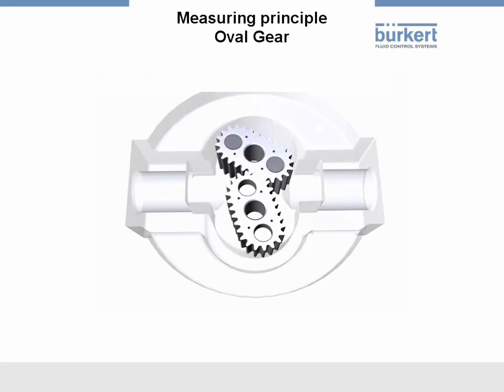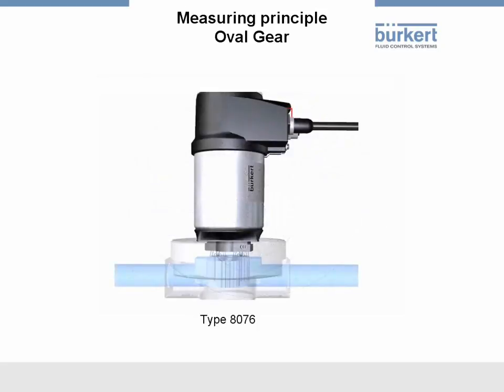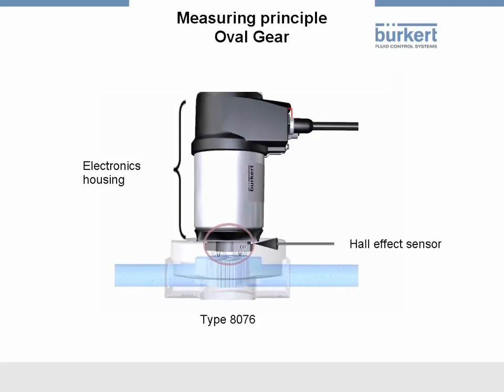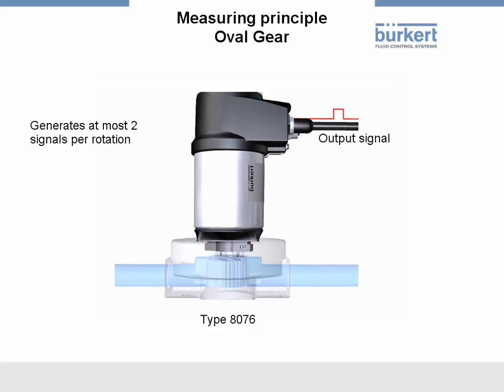To measure the rotary movement, a permanent magnet is attached to each oval gear. In an electronics housing outside of the medium area, there's a Hall effect sensor, which measures the magnetic field of the oval gear and generates at most two signals per rotation. The electronic circuit generates a rectangular signal. The number of pulses is directly proportional to the number of conveyed chamber volumes.